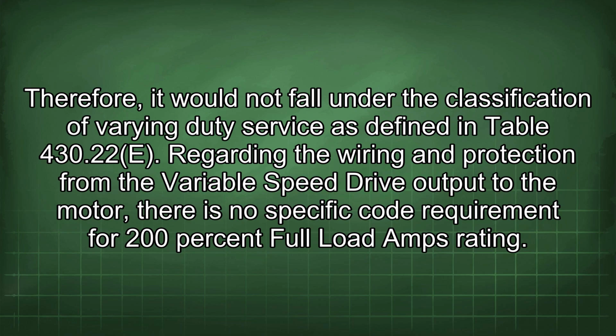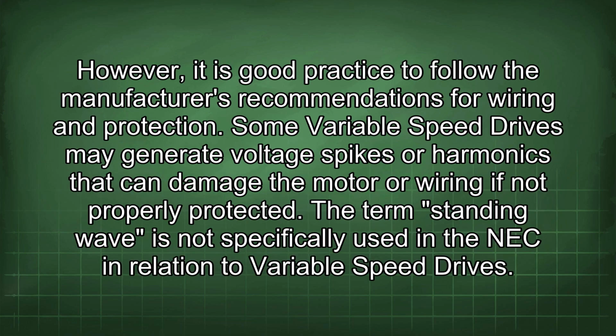430.22e. Regarding the wiring and protection from the variable speed drive output to the motor, there is no specific code requirement for 200% full load amps rating. However, it is good practice to follow the manufacturer's recommendations for wiring and protection. Some variable speed drives may generate voltage spikes or harmonics that can damage the motor or wiring if not properly protected. The term standing wave is not specifically used in the NEC in relation to variable speed drives.